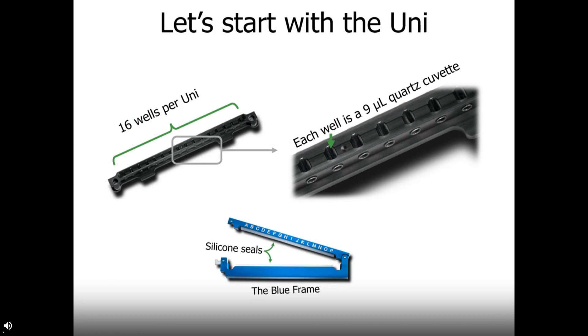The secret sauce of UNCLE is the UNI — an anodized aluminum frame with 16 quartz cuvettes, where each quartz cuvette holds 9 microliters of sample. You just pipette in your sample and seal the UNI inside of its blue frame so silicone seals clip around those little cuvettes. Just like that, you have a nicely sealed sample where you don't have to worry about evaporation over long periods of time or over a thermal ramp. You can pop it into a 37-degree incubator and do a weeks- or months-long stability experiment right in the UNI, or put it into a freezer and go through freeze-thaw cycles also right in that UNI.